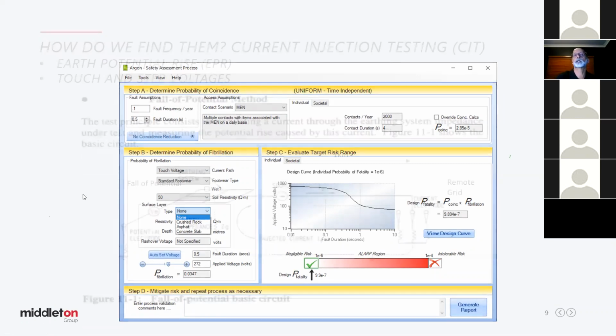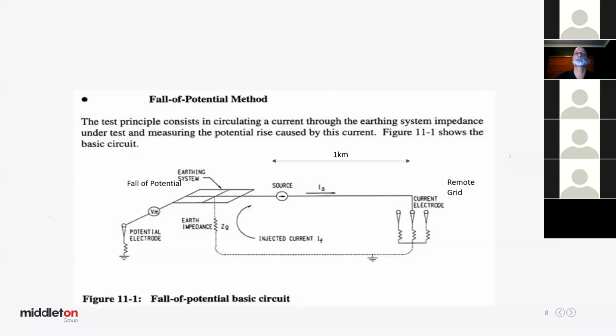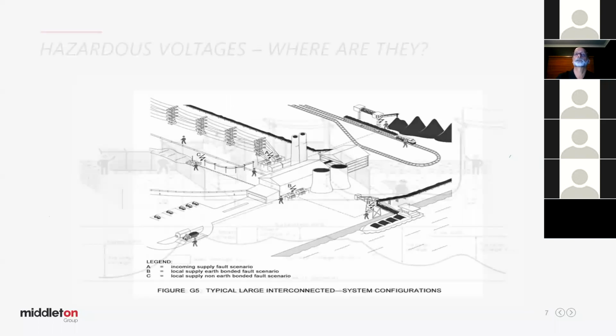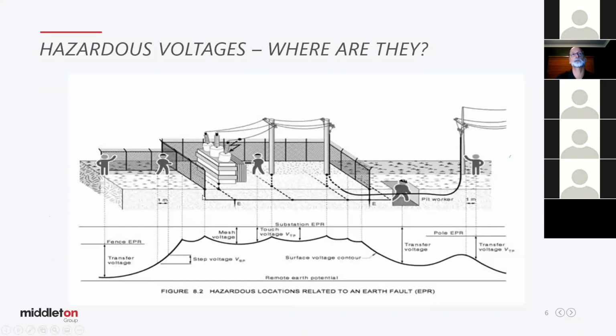So if we looked at where we can see the voltages and we've measured those voltages, what's a safe voltage? Perhaps just let me quickly go back, for explanation reasons, to our graph here. We mentioned it back then, but to put you back in the picture, we can measure voltages between the soil, where this fellow's standing, and on fences, with our frequency tuned voltmeter. This is our fall of potential that we measured, point by point. So we've set up our current, we've measured our EPR, we've measured our test voltages around here, our touch voltages. How do we know that the voltages we've measured on this fence are safe?